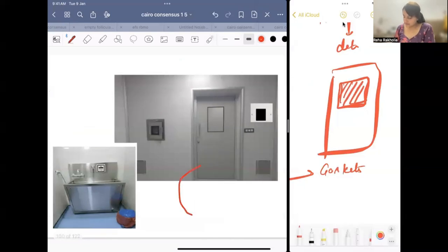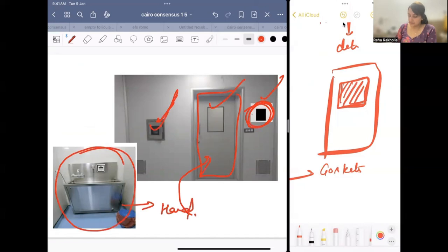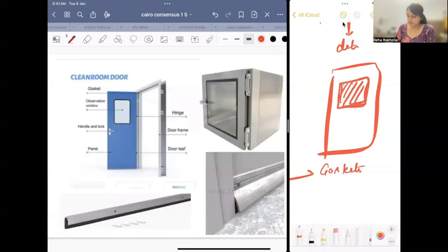As we enter the IVF lab, this is the door, totally sealed, and this is the pass-through, and this is the pressure sensor. I have made a diagram to remember these points: doors should be sealed with a bottom sweep, a sealed pass-through, and a pressure sensor near the door, with the hand washing area outside the door for clean room doors.